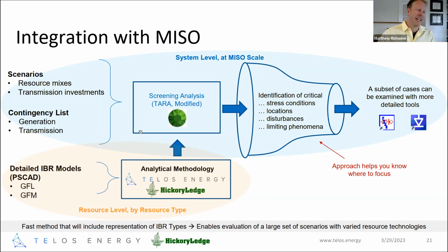Now, instead of having all these resources appear identical and idealized—except maybe for rating—with that idealized voltage-regulating characteristic, we can introduce a dynamic impedance to capture behavior, derived from detailed resource models through electromagnetic transient simulation, for instance in PSCAD, for resources like grid-following or grid-forming inverters, StatComs, you name it. It doesn't matter what label you apply, as long as you perform that characterization and generate a representative dynamic impedance that can be fed into this analysis.